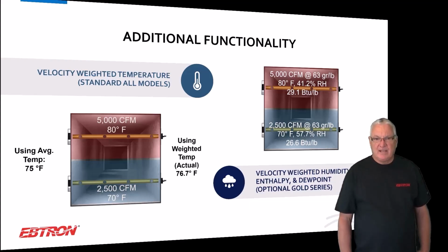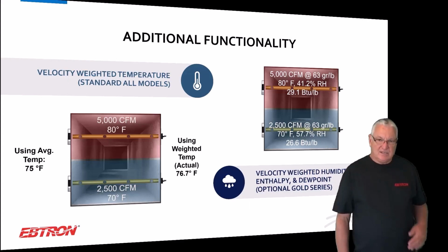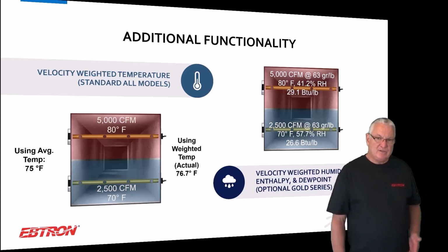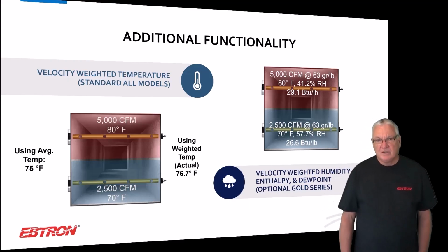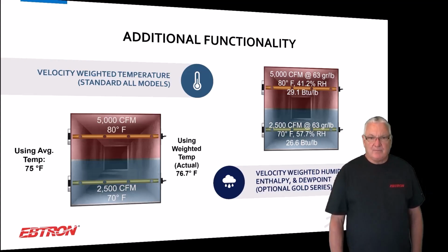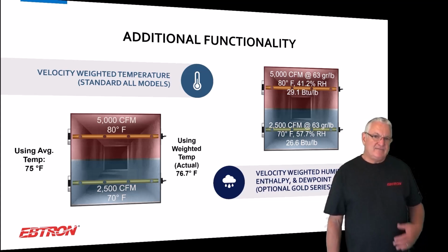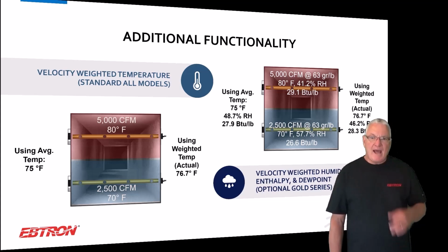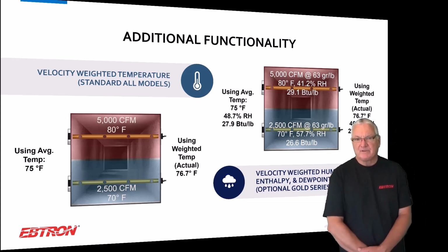and the bottom of the duct is 58% RH. I mean, I'm rounding, but the big deal is the BTUs per pound. If you were using this for wet bulb switchover, the top of the duct's 29.1 BTUs per pound. You're not economizing. The bottom of the duct is 26.6 BTUs per pound. You are. So where did you locate your enthalpy sensor? And the bottom line is, even if you use the average temperature, it's not right. You have to use velocity weighted temperature.